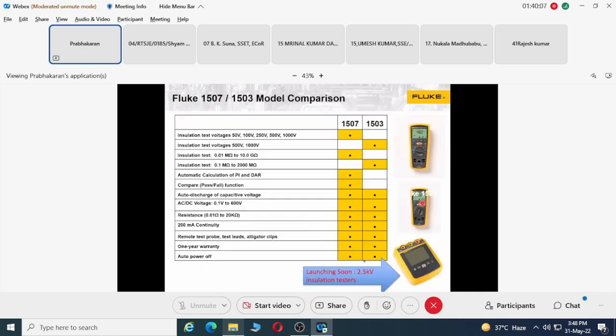And here we can share these two models. These two models are actually very popular insulation testers from us, and you can see the insulation test voltages. With a single press, you will be able to get what voltage levels you want, and then the 1507 and 1503 will be able to give you the voltage level. Even the 1503 can give you two voltage levels, 500 and 1000 volt. Here you can get multiple choices, 50 volt to 1000 volt ranges. And the insulation range also is very high, that is 10 gigaohm of resistance in this model and 2000 megohm in this model. Okay, that means a detailed insulation portfolio analysis can be done using these products.